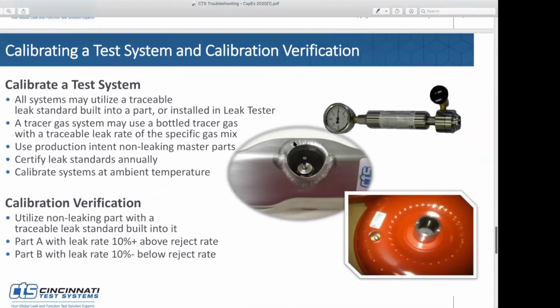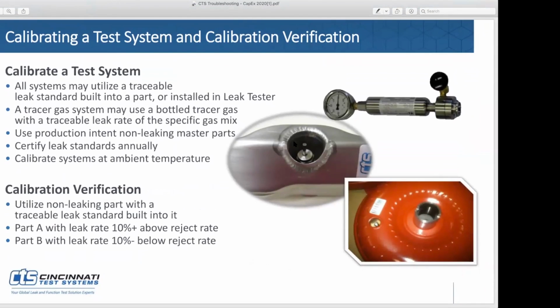So now you've calibrated your system, and that's something to understand: every time you make a change to your system, you want to recalibrate it. To validate or verify you've got a good calibration, check your performance factor first, and then you can have a mastered part with a leak standard built into it, 10% above and 10% below your reject rate. So that's two additional master parts, one above, one below your reject rate. Test those and make sure you accept the one that is below and reject the one above, and that you're measuring within that percentage window for the expected leak rate or measurement of those parts.